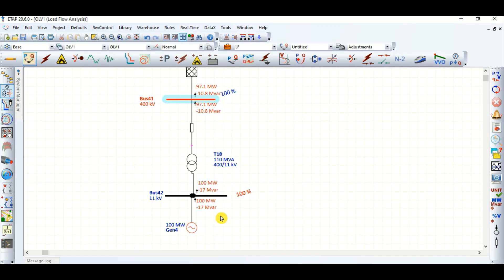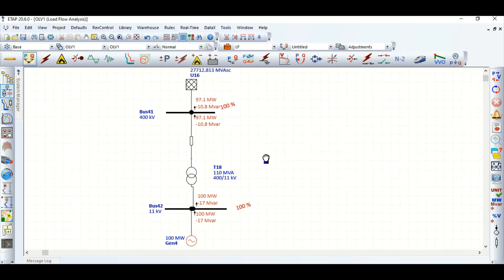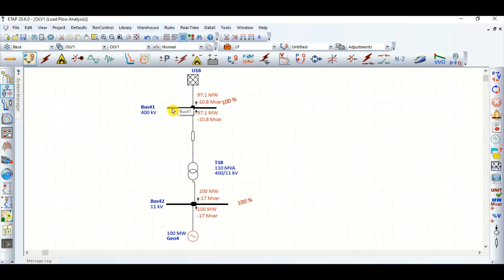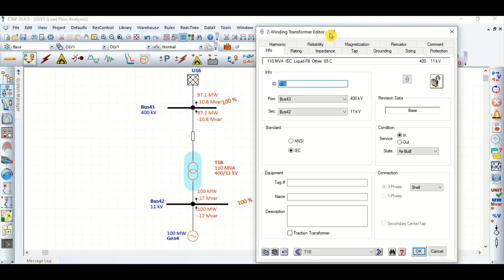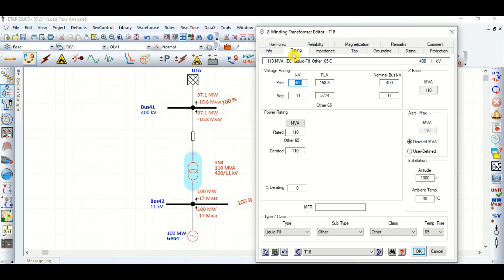In real project study cases, on the 400 kV side, the transformer — basically the generator step-up transformer (GSUT) — its primary side voltage is considered 5% higher than the bus voltage. Since the bus voltage is 400 kV, 5% means 420 kV.